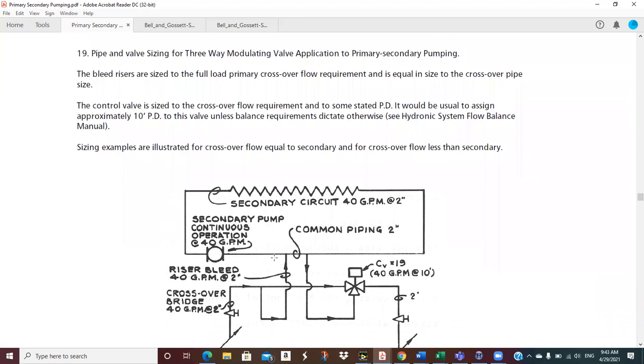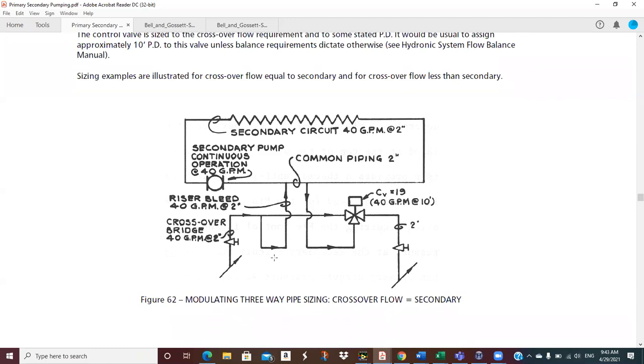Okay, so here's an example of just actually doing the CV sizing. And of course, you know what I did, I left my calculator in the classroom, but we know this equation. So you see here, this is the chilled water application where I got 40 GPM everywhere. And to size that CV, and again, our sizing criteria here, they're showing as a minimum of 10 feet across that valve. Okay, so to calculate that 19, what do you do? You take 10 feet and divide by 2.3 to get it in PSI. You take the square root of it. We're taking specific gravity to be 1 here. So you just take the square root of that and you get 2.08.